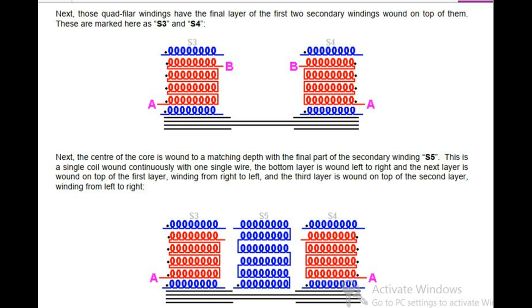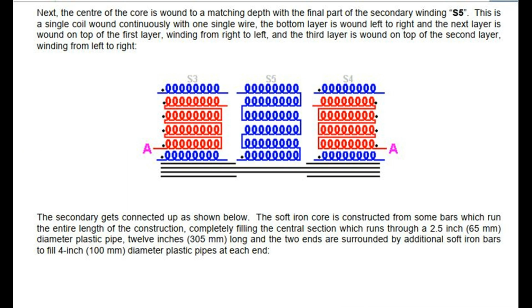Next, the center of the core is wound to a matching depth with the final part of the secondary winding S5. This is a single coil wound continuously with one single wire. The bottom layer is wound left to right and the next layer is wound on top of the first layer, winding from right to left, and the third layer is wound on top of the second layer, winding from left to right. The secondary gets connected up as shown below.